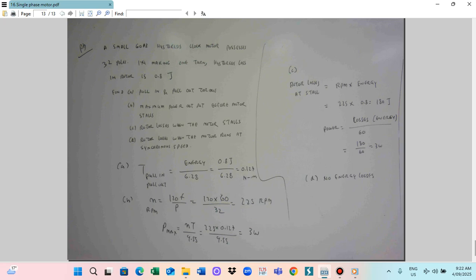And B means the motor synchronous speed has the maximum power output before the motor stalls. So in this case, the maximum power needs to be calculated. P is N times T divided by 9.55. So in this case, you have to find the synchronous speed. Ns is 120 f divided by P, in RPM. So 120 times frequency 60 Hz, number of poles is 32, so you get 225 RPM.